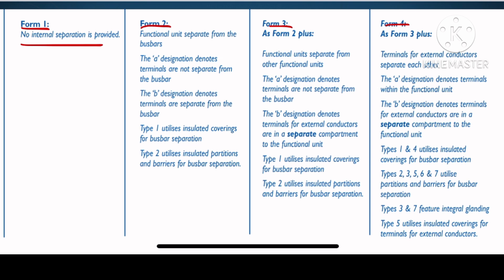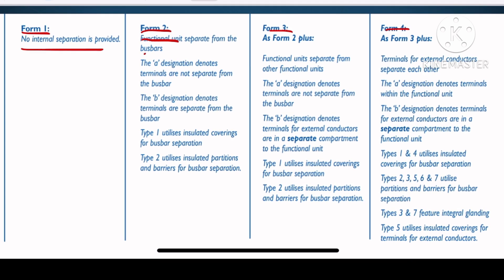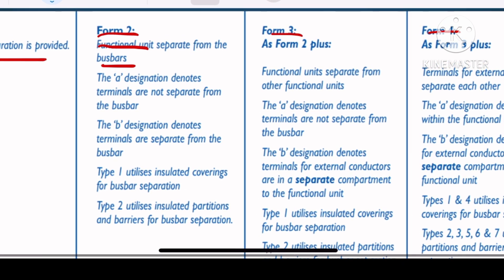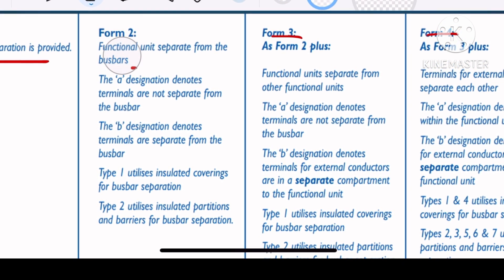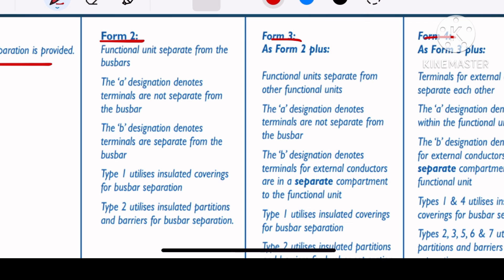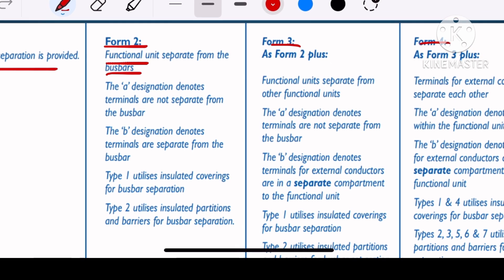For form 1, there is no separation at all — between bus bar and functional unit, functional unit to functional unit, and terminals to terminals, there is no separation. In form 2, there is only one separation: the separation between the functional unit and the bus bar.